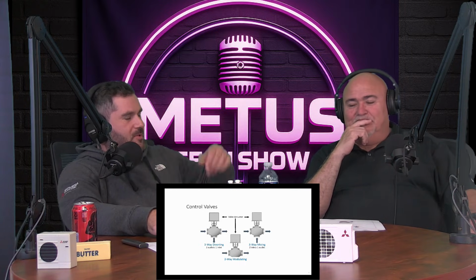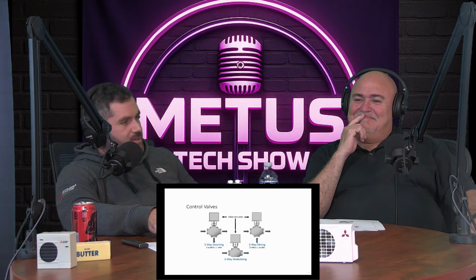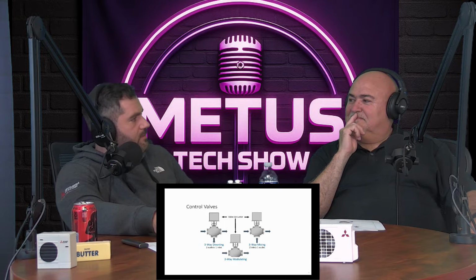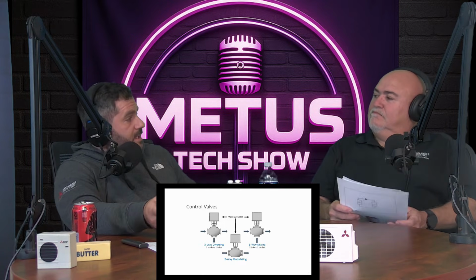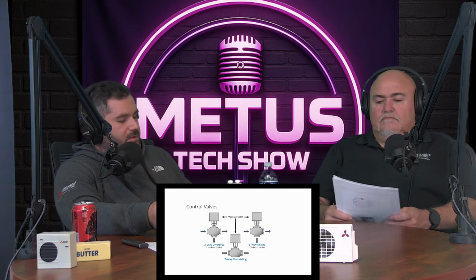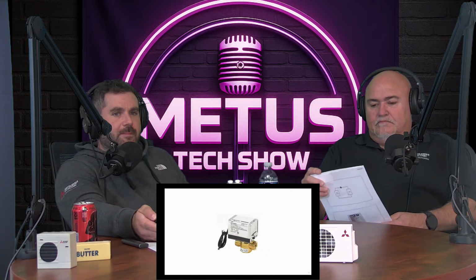Yeah, so those are pretty common. You probably have the old school honeycomb style, as we used to call them, Taco zone valves, with a manual lever that you've got to really crank down to get the thing to open up. But those are nice because they have 3 terminals, so they can act as your end switch. The nice thing about it is you don't need a zone controller for those. You just need a transformer, and that's going to help power your end switch. So if any one of them were to call or open, it's just going to send that end switch down to the boiler to say, hey, come on, I have a zone calling. Whereas newer zone valves, some of them are set up that way, but some of them are just 2-wire, and they only get an on-off signal, and typically you're going to use those with something like a zone valve controller. Right. So just a quick peek at what some of those might look like.